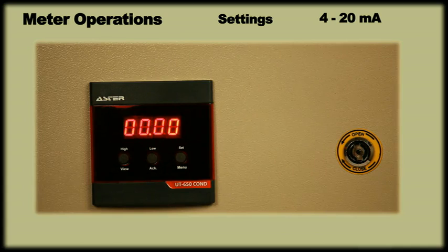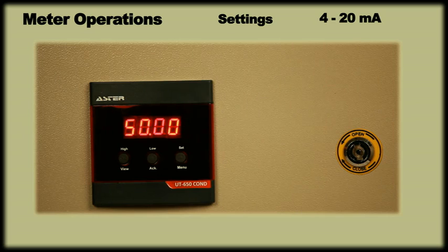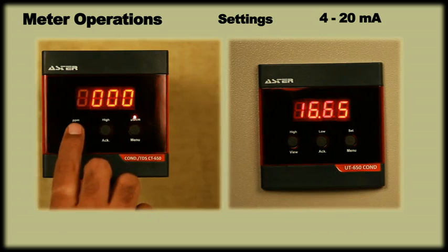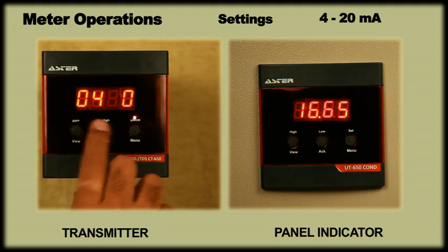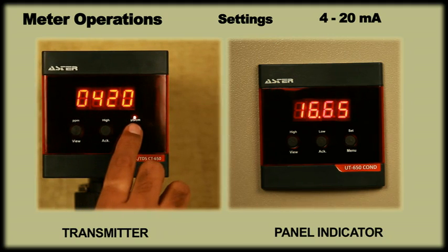Note, the meter has an inbuilt 4 to 20 mA output simulator for easy synchronization with the PLC or any other remote device. To output standard 4 and 20 mA, enter password 0420.